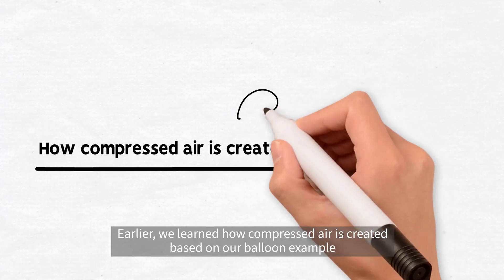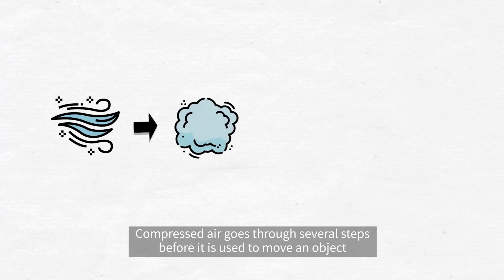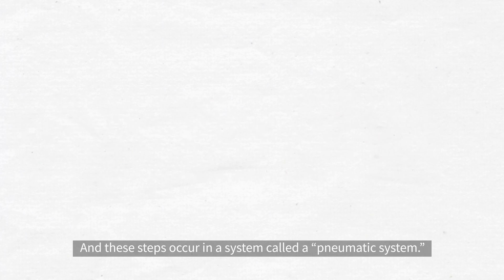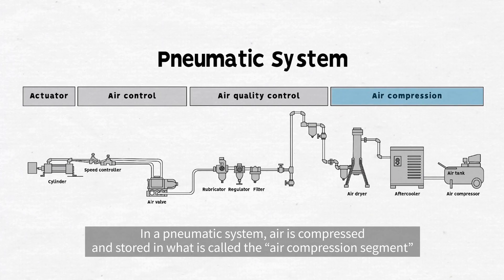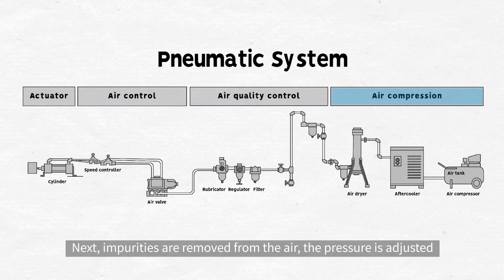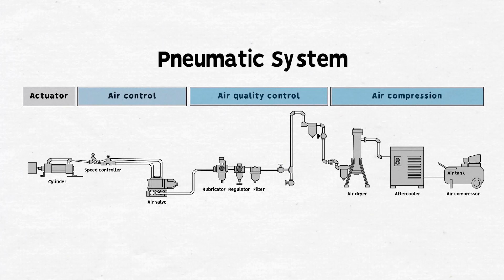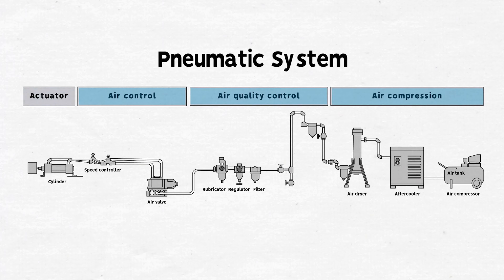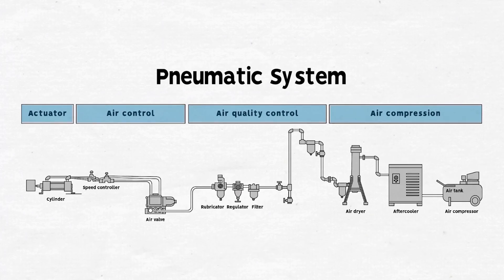Earlier, we learned how compressed air is created based on our balloon example. Compressed air goes through several steps before it is used to move an object, and these steps occur in a system called a pneumatic system. In a pneumatic system, air is compressed and stored in what is called the air compression segment. Next, impurities are removed from the air, the pressure is adjusted, and other conditions of the compressed air are adjusted in the air quality control segment. Then, the direction and speed of the air movement are controlled in the air control segment. Finally, the segment that moves an object is called the actuator segment.